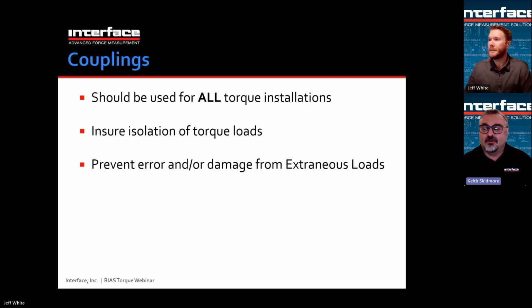So couplings should be used for all torque installations. Some people say, oh, why do I need to use couplings with a reaction torque sensor? Well, we use them in our calibration rig, for example, when calibrating reaction torque sensors. They should be used. They sometimes aren't. The customer does that at their own jeopardy.